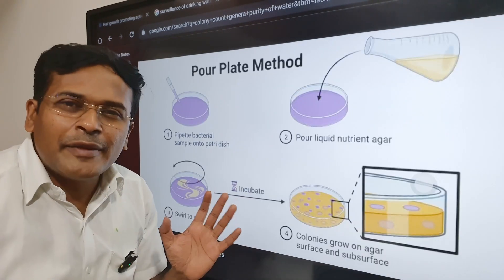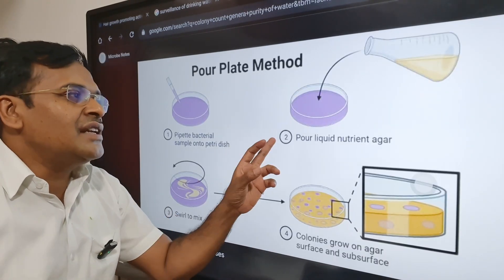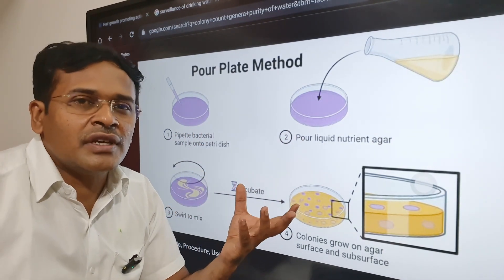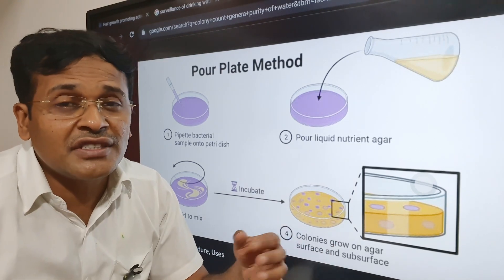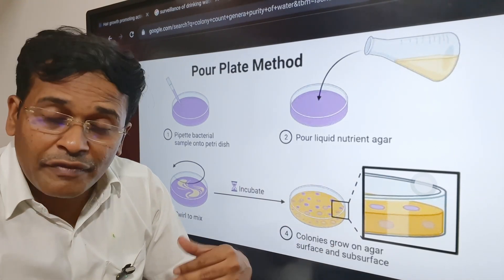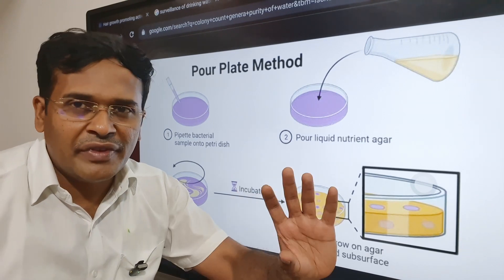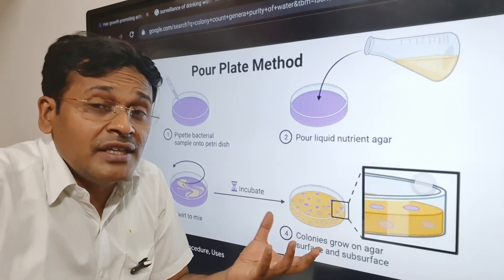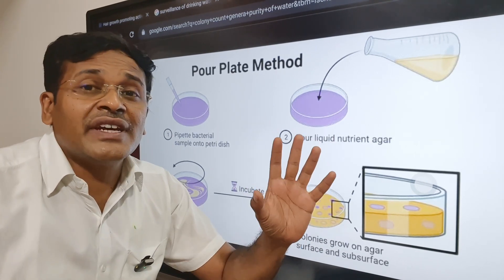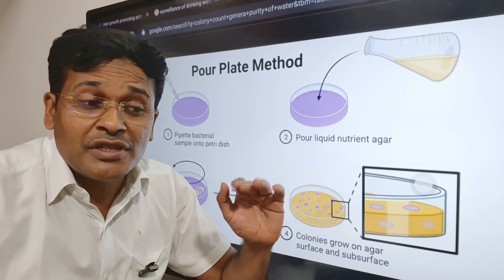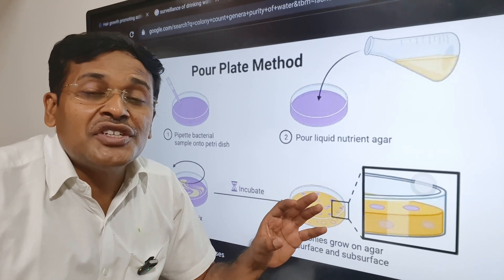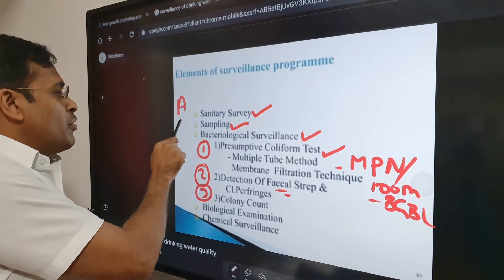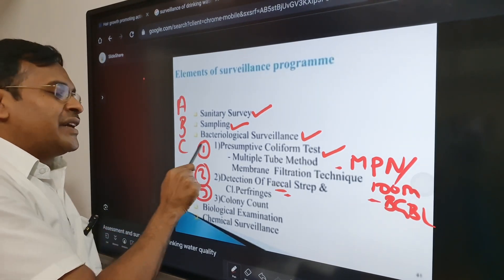The third bacteriological test is colony count using the plate method. In yeast extract agar, water is poured and colonies are observed at 22 degrees Celsius after 24 hours, 48 hours, and seven days. This is used for maintenance monitoring — a sudden increase in colony count indicates real contamination of water, allowing early detection.